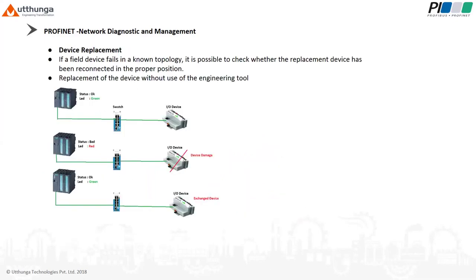Device replacement. If a device fails in a topology, it is possible to check whether the replacement device has been reconnected in the proper position. It is even possible to replace a device without the use of an engineering tool. In the picture itself, it's clear that first the device was working fine, in the second the device was not working fine, then we will change it with a new device with the same spec. Then the controller will automatically detect the device and provide a name also, and moreover it will start the communication immediately.